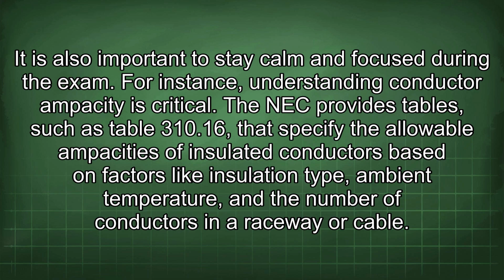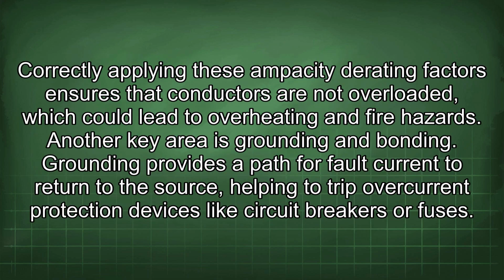For instance, understanding conductor ampacity is critical. The NEC provides tables, such as Table 310.16, that specify the allowable ampacities of insulated conductors based on factors like insulation type, ambient temperature, and the number of conductors in a raceway or cable. Correctly applying these ampacity derating factors ensures that conductors are not overloaded, which could lead to overheating and fire hazards.